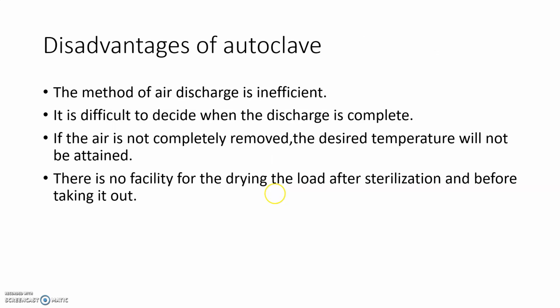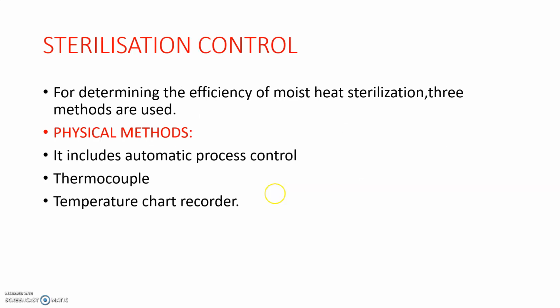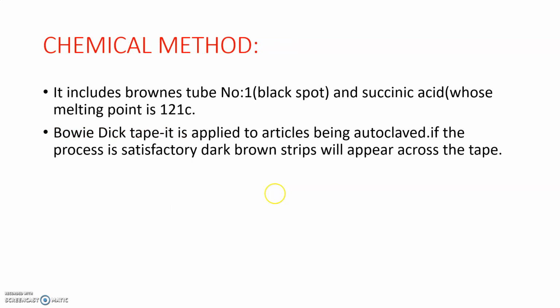Now, what are the disadvantages of the autoclave? This method of air discharge is inefficient and it is difficult to decide when the discharge is complete. If the air is not completely removed, the desired temperature will not be attained, and there is no facility for drying the load after sterilization and before taking it out. Now, different methods of sterilization control are mentioned, that is, physical methods to determine the efficiency of moist heat sterilization. Physical methods include automatic process control, thermocouple, and temperature chart recorder. Chemical methods include Browne's tube number 1 that shows a black spot, and succinic acid whose melting point is 121 degrees Celsius, and this melting takes place if the sterilization is efficient.